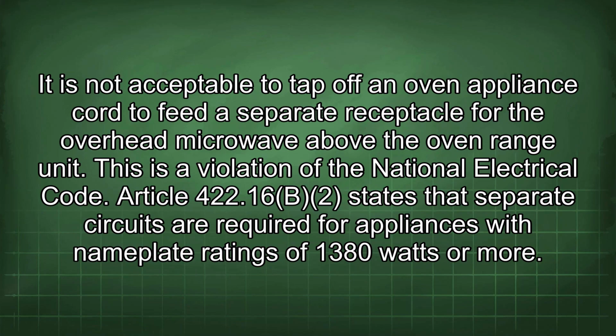It is not acceptable to tap off an oven appliance cord to feed a separate receptacle for the overhead microwave above the oven range unit. This is a violation of the National Electrical Code. Article 422.16b2 states that separate circuits are required for appliances with nameplate ratings of 1380 watts or more.